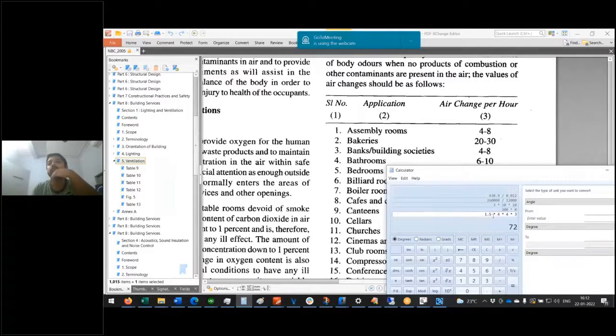Okay, so 1.5 per window, that is the area of the opening, 4 number of windows, 4 walls. So this is my opening area times 3 meter per second, which is the velocity that I want, right? If I multiply that, I get 72 cubic meter per second. This is the minimum that is required. Please note this is cubic meter per second.